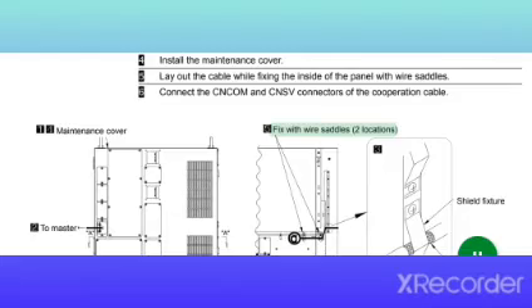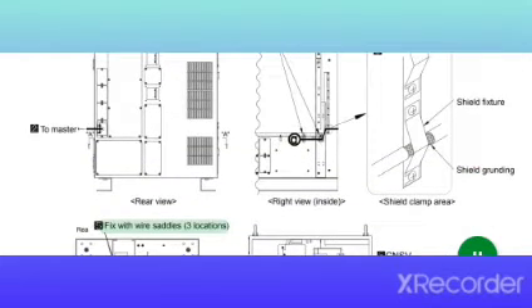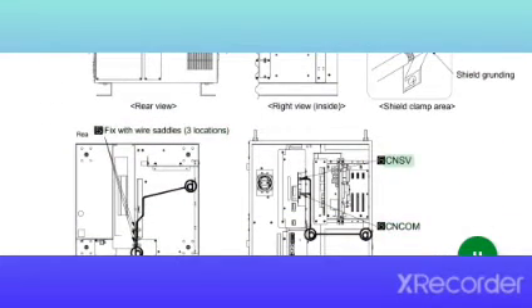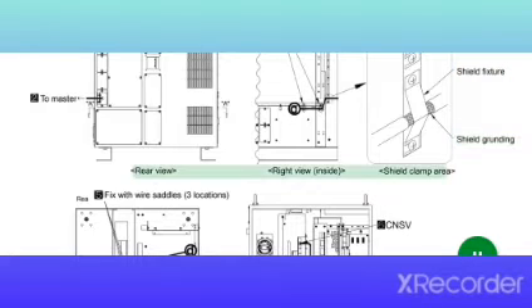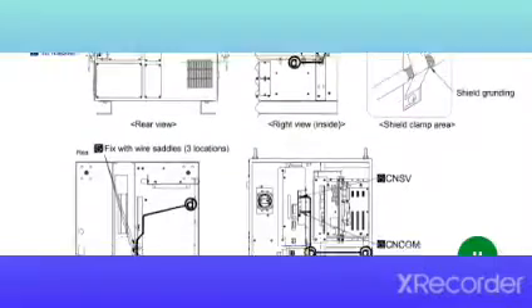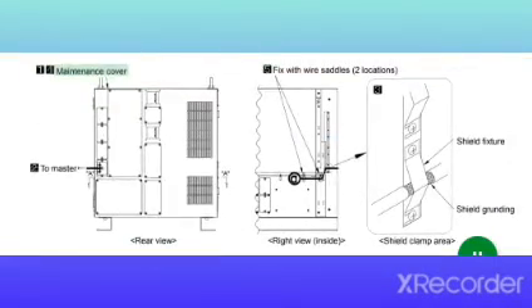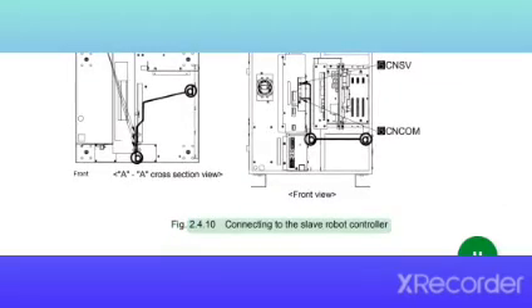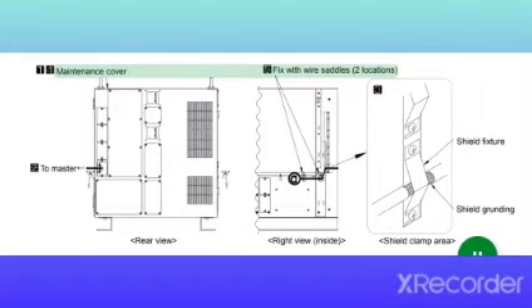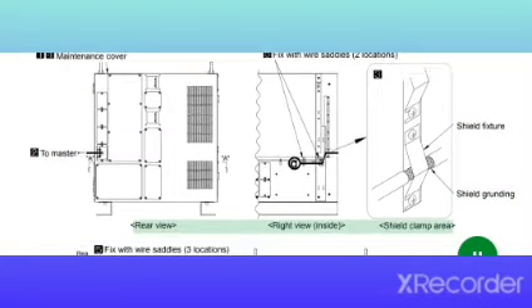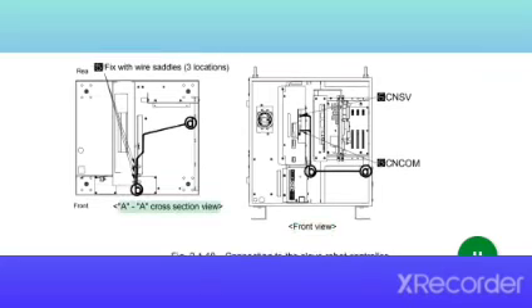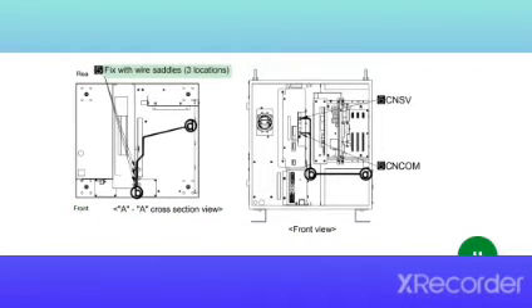Fix with wire saddles, 2 locations. Fix with wire saddles, 3 locations. CNCOM, CNSV, shield fixture, shield grounding, rear view, right view, inside shield clamp area, cross-section view, front view, front, rear, maintenance cover. Fig. 2.4.10 Connecting to the slave robot controller. To master, shield fixture, shield grounding, front view.